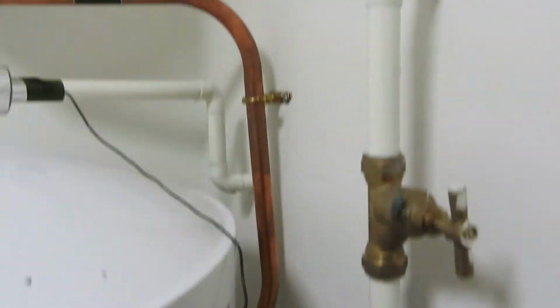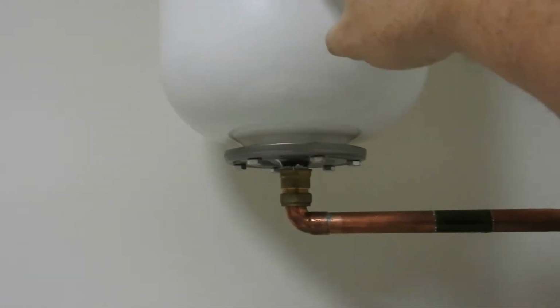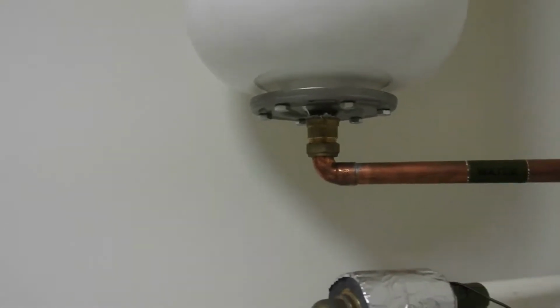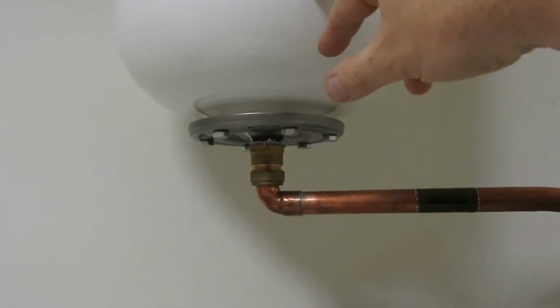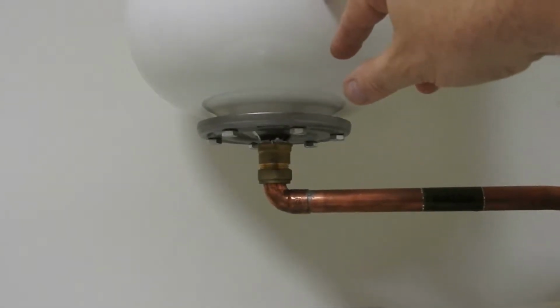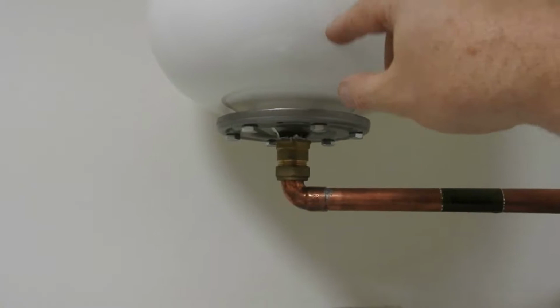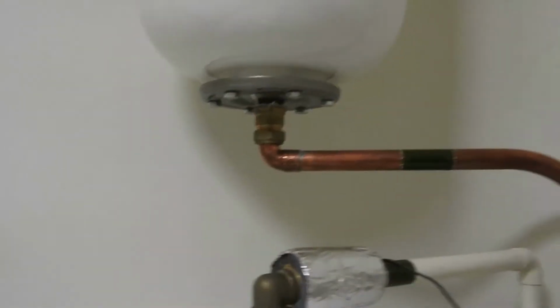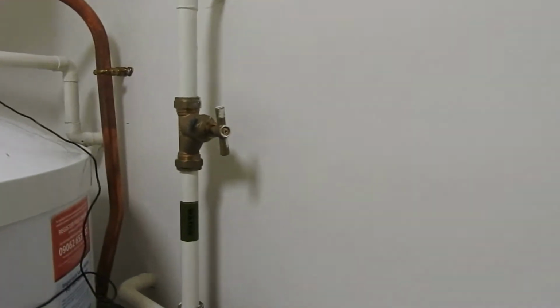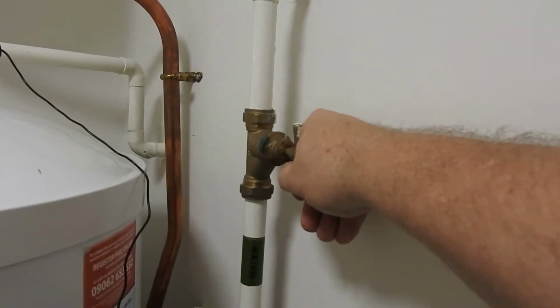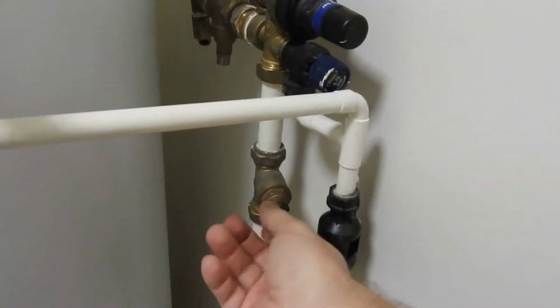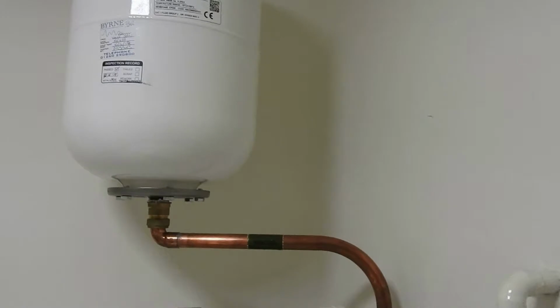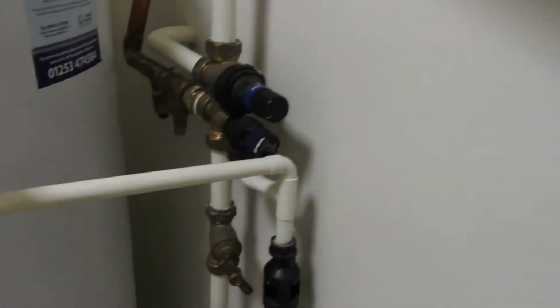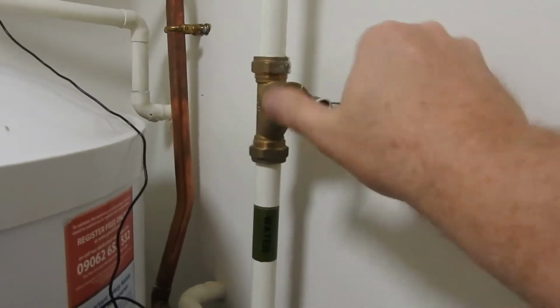That was the water that had expanded into this vessel to make sure nothing explodes. Now clearly, water that doesn't go anywhere, that's lovely and warm and is in there for a week, has the potential to have Legionella in it. So we're disposing of that. And then we're turning the system back on again. And everything is now free to expand and move within this sealed system. One other thing to do, let's just close this off again.